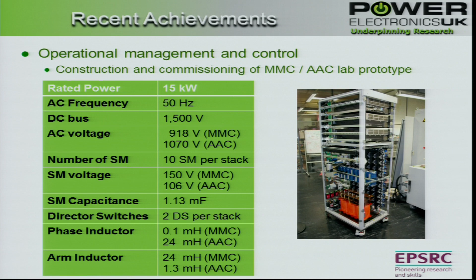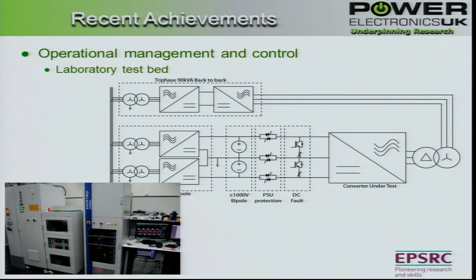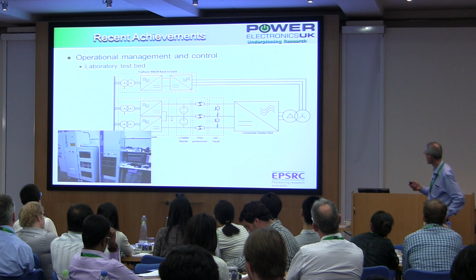Some test results are starting to come from this. This is the test bed at Imperial, where the converter under test sits. There's a grid link converter system, a back-to-back converter system to give a controllable, isolated AC voltage for the AC side of the converter under test. There's a DC circuit with a capability for putting faults onto the DC link, and another converter that can take the power back to the grid, so power can be passed either way, providing a flexible way of testing the converter under test. And there are some lab pictures there.